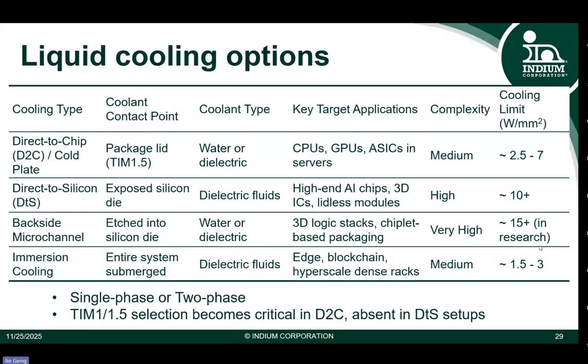Another option is direct-to-silicon liquid cooling. In this case, either microchannels are etched inside the silicon chip or on the back of the silicon chip, and the fluid flows directly to the silicon chip. This can give you very high thermal performance, but right now the process is expensive, and a lot of reliability tests still need to be done for this type of direct-to-silicon cooling.